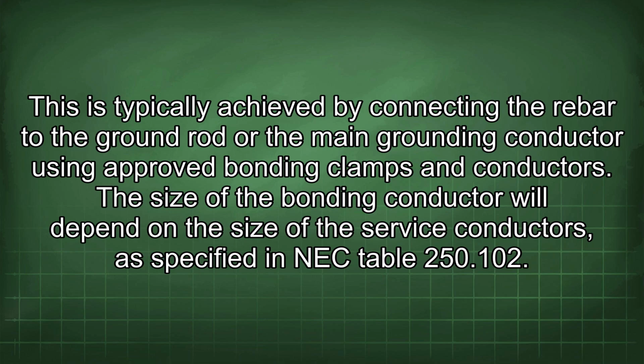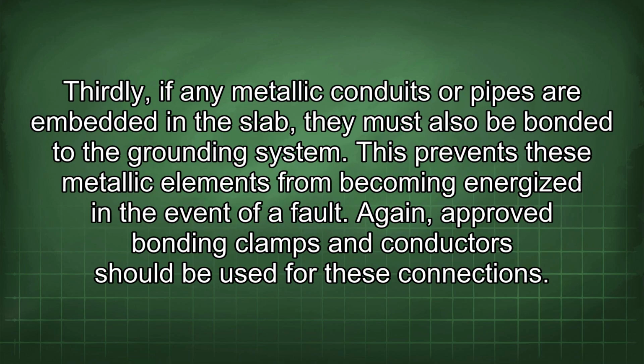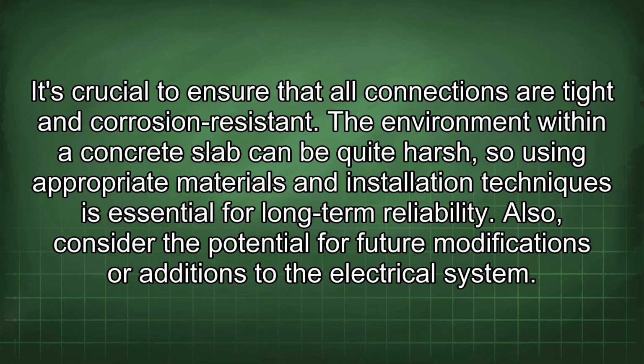The size of the bonding conductor will depend on the size of the service conductors, as specified in NEC Table 250.102. Thirdly, if any metallic conduits or pipes are embedded in the slab, they must also be bonded to the grounding system. This prevents these metallic elements from becoming energized in the event of a fault. Again, approved bonding clamps and conductors should be used for these connections. It's crucial to ensure that all connections are tight and corrosion resistant. The environment within a concrete slab can be quite harsh, so using appropriate materials and installation techniques is essential for long-term reliability.